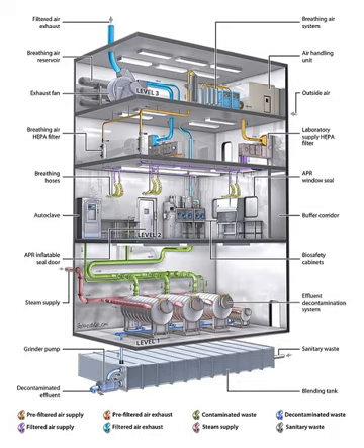Biosafety level 4 is the highest level of biosafety precautions, and is appropriate for work with agents that could easily be aerosol transmitted within the laboratory and cause severe to fatal disease in humans for which there are no available vaccines or treatments. BSL-4 laboratories are generally set up to be either cabinet laboratories or protective suit laboratories. In cabinet laboratories, all work must be done within a class 3 biosafety cabinet. Materials leaving the cabinet must be decontaminated by passing through an autoclave or a tank of disinfectant.